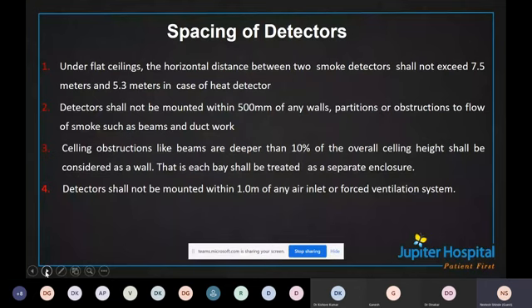So if any wall or partition obstruction is there, the smoke detector should be kept away by 500 mm. So it is 0.5 meter. When we say 1 meter is around 3 feet, 300 mm is 1 foot, so 500 mm is just near to 2 feet distance. It should not be mounted within 500 mm.